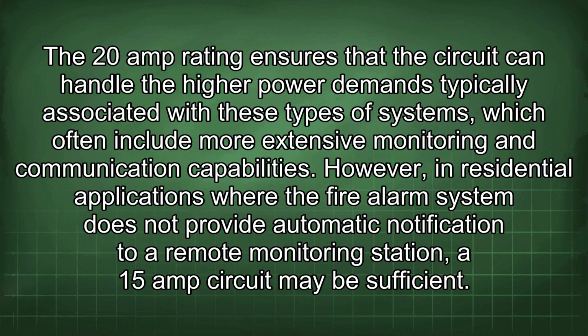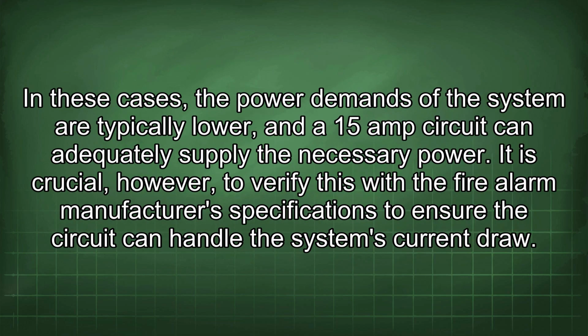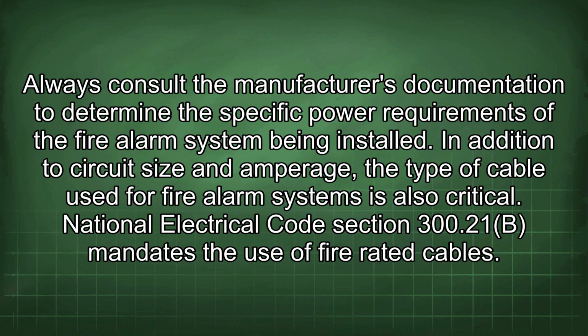However, in residential applications where the fire alarm system does not provide automatic notification to a remote monitoring station, a 15-amp circuit may be sufficient. In these cases, the power demands of the system are typically lower, and a 15-amp circuit can adequately supply the necessary power. It is crucial, however, to verify this with the fire alarm manufacturer's specifications to ensure the circuit can handle the system's current draw. Always consult the manufacturer's documentation to determine the specific power requirements of the fire alarm system being installed.